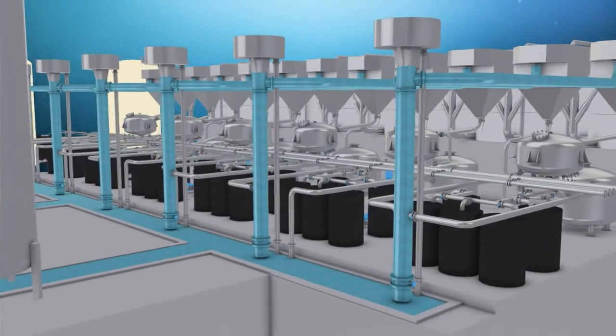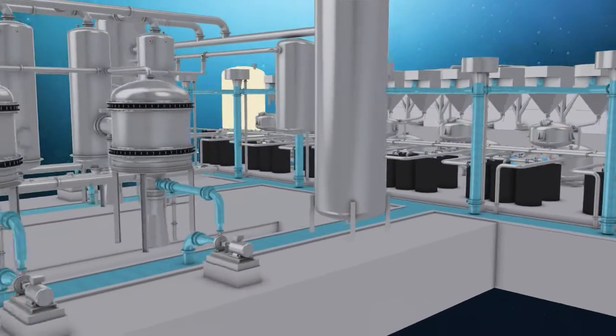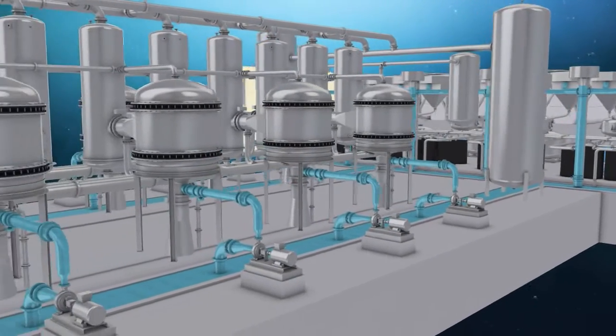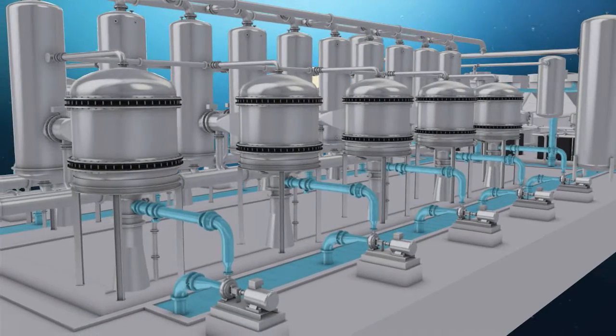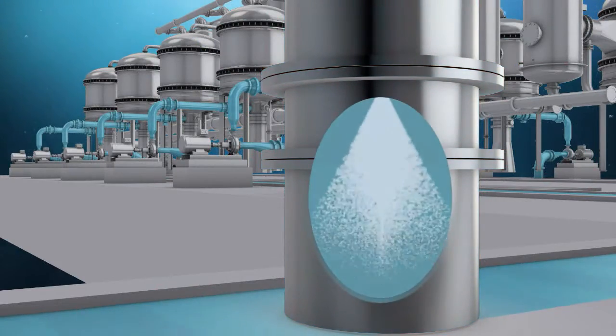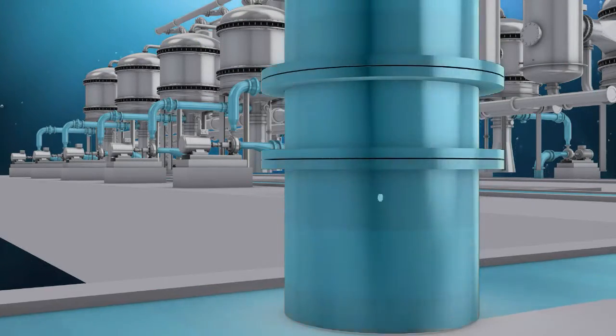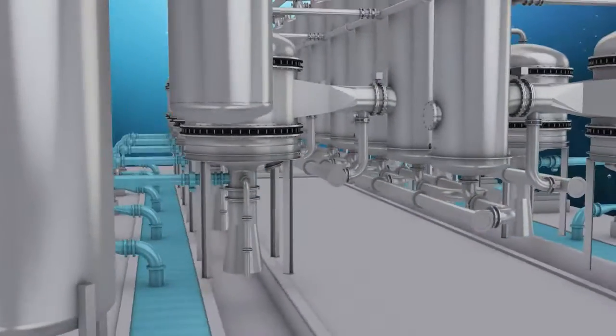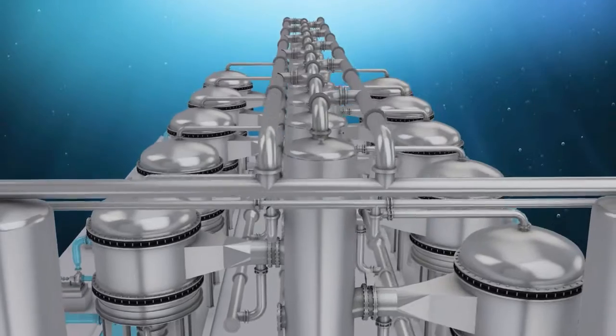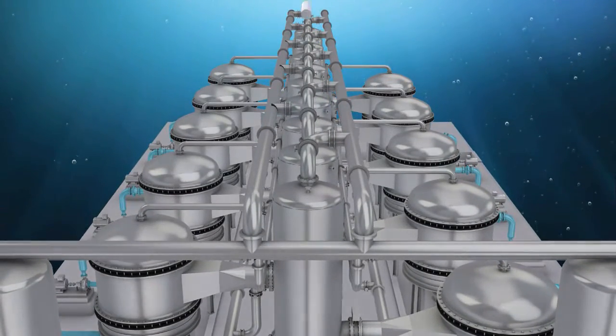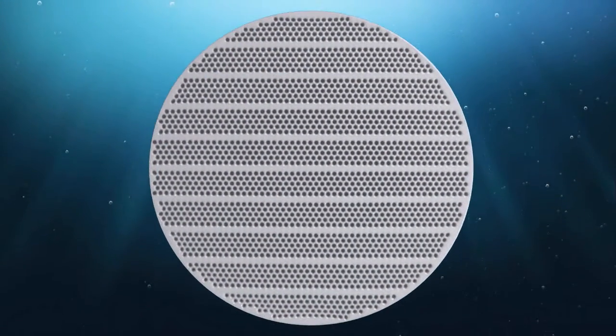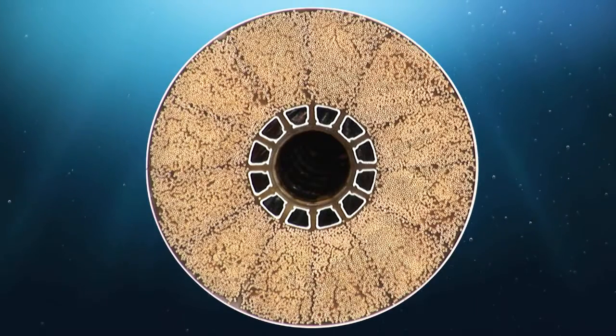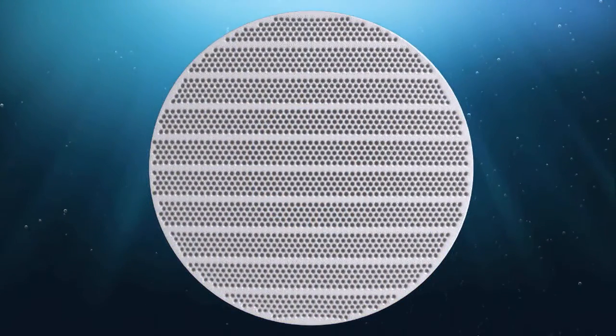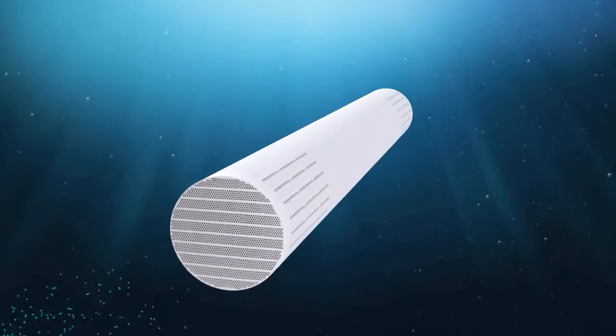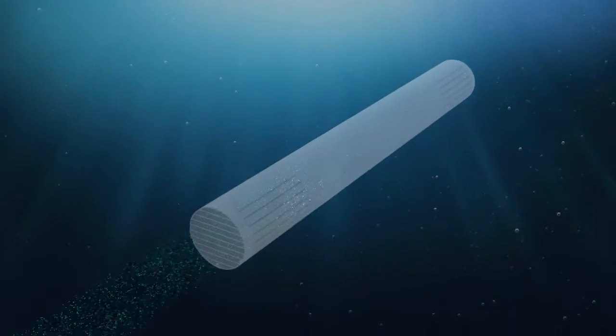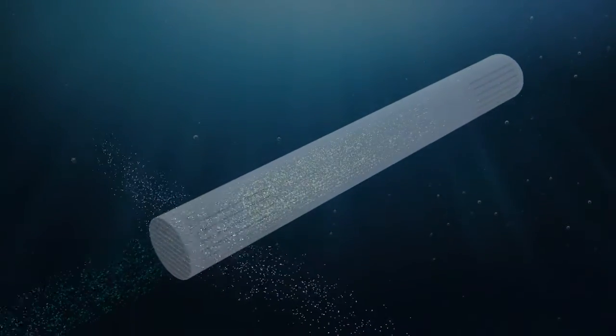The treated water flows from 6 to our next innovation, Ceramac, a ceramic microfiltration process to remove all suspended matter. In between, hydrogen peroxide is added to the water for the UV peroxide treatment later on. By adding it in front of the Ceramac installation, it will also reduce biological fouling of the membranes. Ceramic membranes have many advantages over standard polymer membrane installations, like no risk of fiber breakage and a very narrow pore size distribution. But the main reason for choosing ceramic membranes is the indefinite lifetime, making it a robust and sustainable solution.